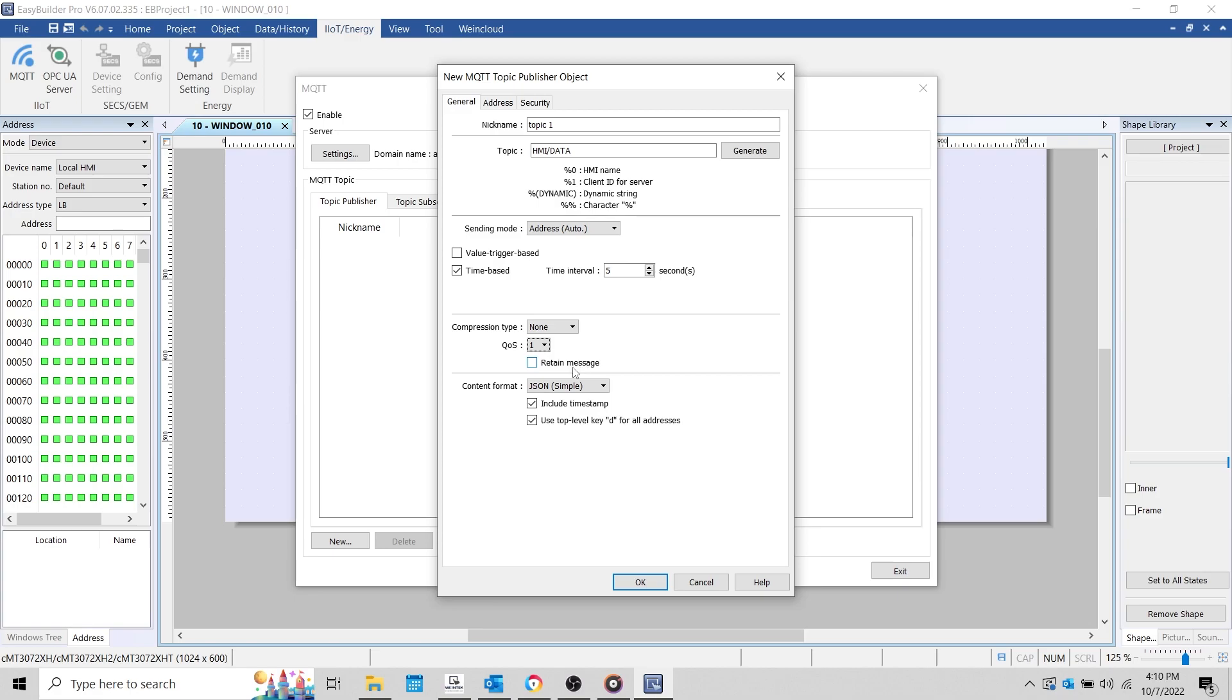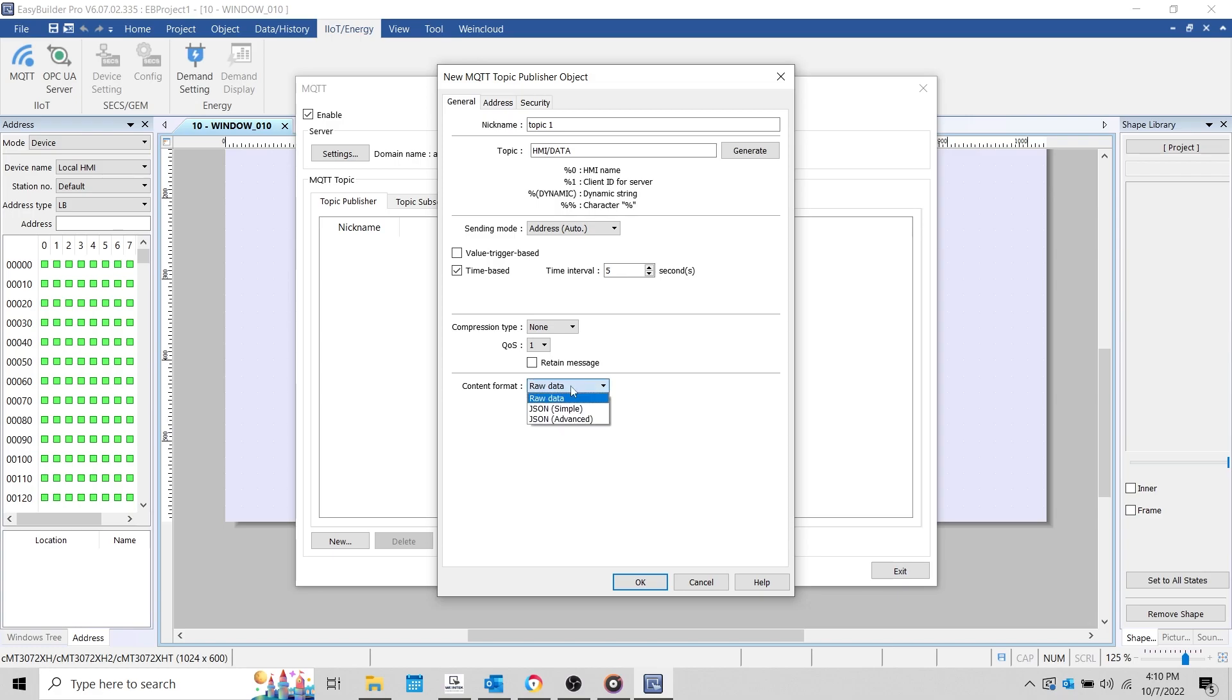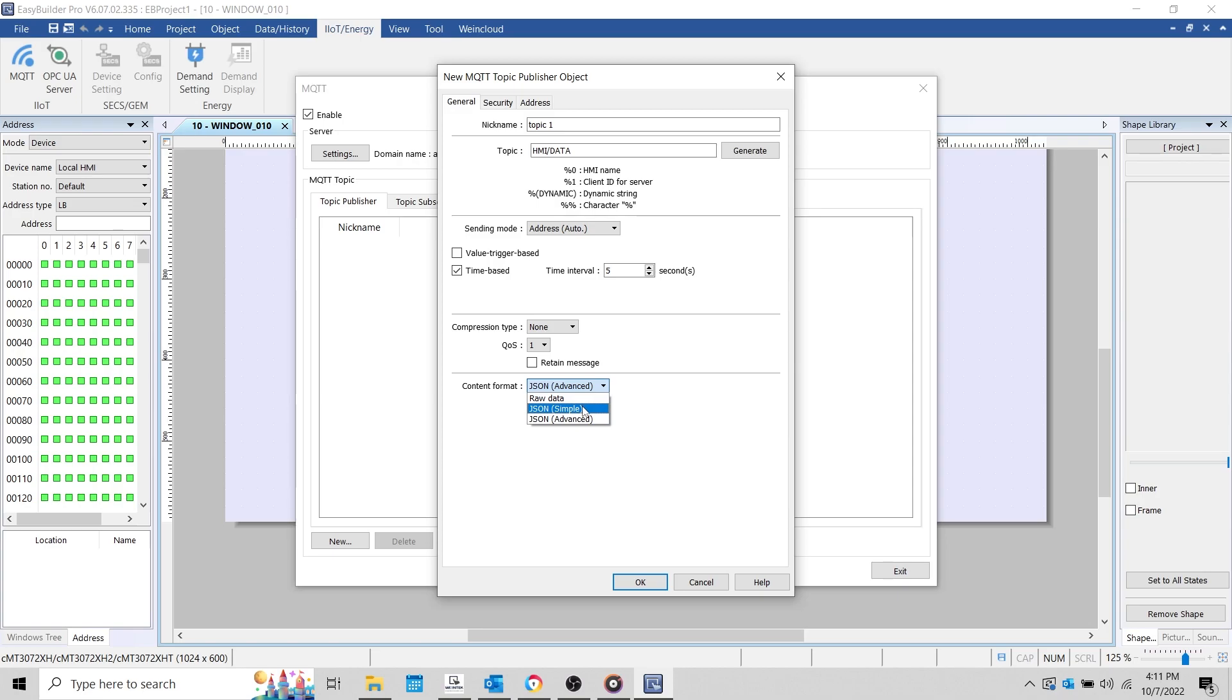The Retain Message option will allow the MQTT server to retain the last message published by the HMI. There are three different ways to format the content of our message. When raw data is selected, our data will be published as an array of bytes. JSON Simple will automatically add the values you intend to publish, and any option selected below, into a message using JSON format. And JSON Advanced will allow you to customize and preview the structure of your JSON message within the Address tab. During this demonstration, we'll create a topic using both JSON Simple and JSON Advanced, starting with our simplified version first.